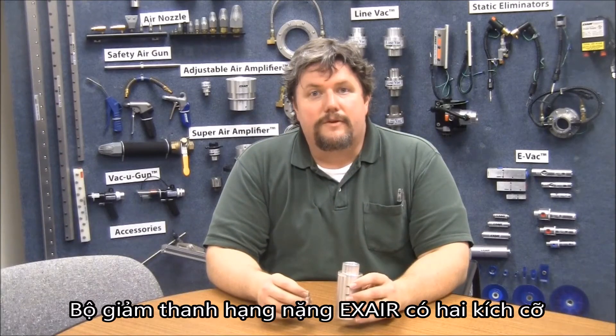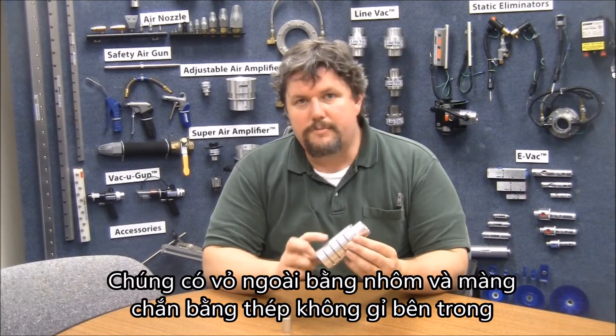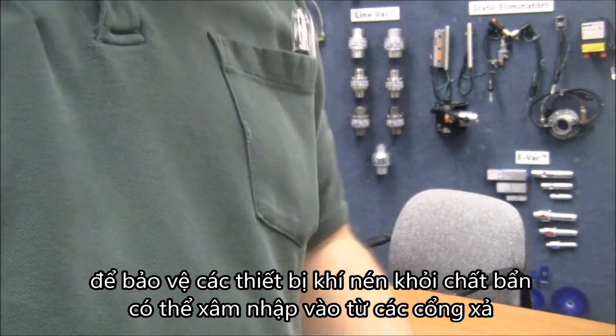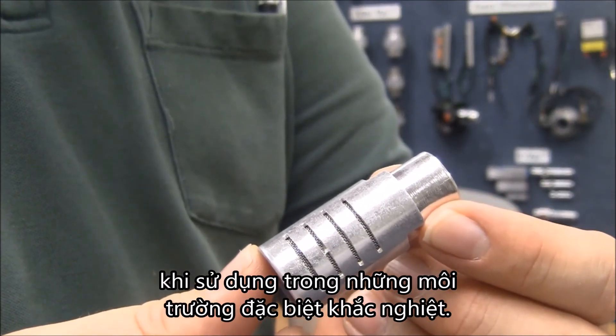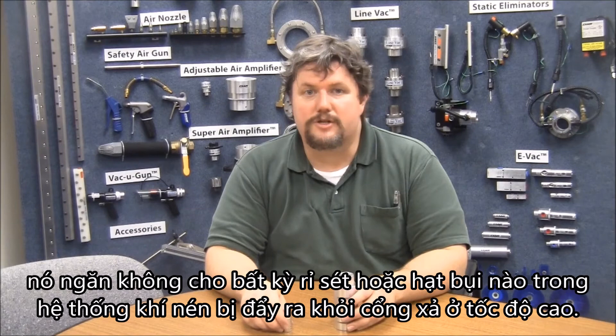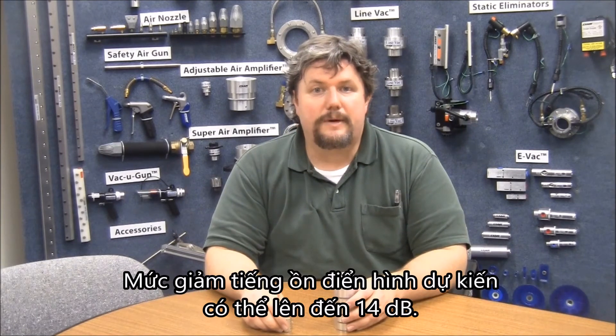EXAIR heavy-duty mufflers are available in two sizes, quarter inch NPT and 3/4 inch NPT. They have an aluminum shell and an internal stainless steel screen that protects pneumatic units from contamination that might enter the exhaust ports when used in particularly aggressive environments. This screen works the other way as well, preventing any air system rust or particulate from being ejected at high speed from the exhaust port. Typical expected noise reduction can be as high as 14 decibels.